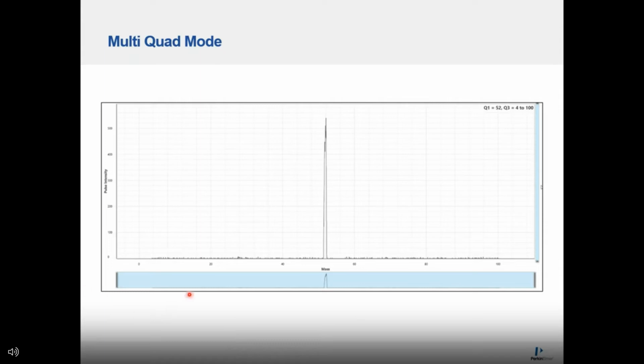see that all previously observed peaks from ammonia and the gas clusters at mass 18 and 35 are removed, leaving a clean analyte signal at mass 52, which is around 500 counts per second, and that corresponds to the real chromium impurity in the samples.